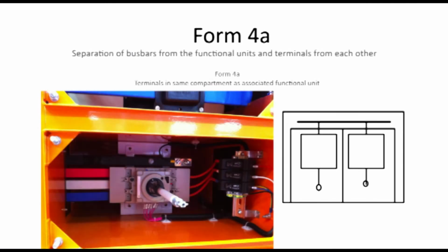When the specifications have been changed, I believe that in some instances 1136 has been deleted and 3439 has been added. This has resulted in an inferior switchboard design than what was really intended. A Form 4A switchboard, in accordance with the current standard, is a Form 3 switchboard to AS 1136 1988.